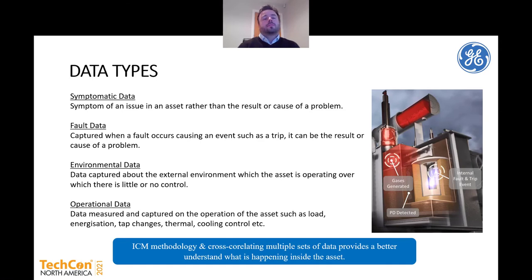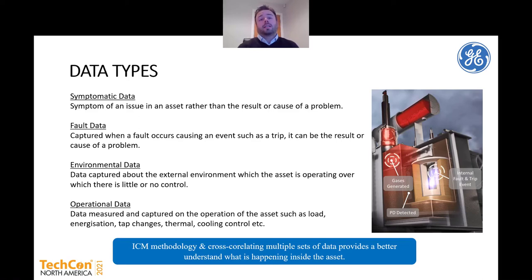When we look at the types of data, there are many different types available. Symptomatic data is a symptom of an issue rather than the cause of the problem — for example, dissolved gases generated in the insulating oil of a transformer, be it the main tank or the LTC/selector diverter tanks. What is causing those gases to be generated? It's not the gas itself that is the fault — it's the symptom of something else that's happening.